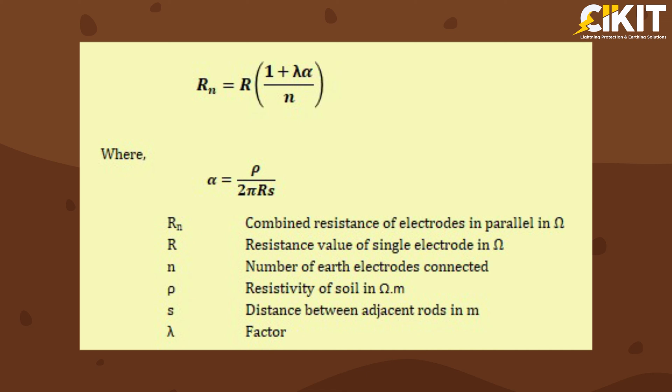If you notice the formula, apart from individual resistance and soil resistivity, spacing between the earth electrodes plays a major role in deciding the combined resistance value of the earth electrodes.